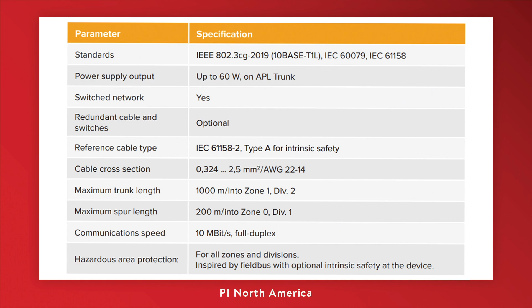So APL is simply a variant of SPE, which is intrinsically safe via adherence to the IEC 60079 two-wire intrinsically safe Ethernet standard. And it's a mouthful, I know, but we simply call it 2-WISE for short. So being intrinsically safe, again, simply means that there is a limitation of voltage on the wire itself so that it cannot, under any circumstance, pose a risk of igniting a spark or explosion in an atmosphere that contains dangerous gases or dust that may be flammable. Again, we're looking at process industry environments.